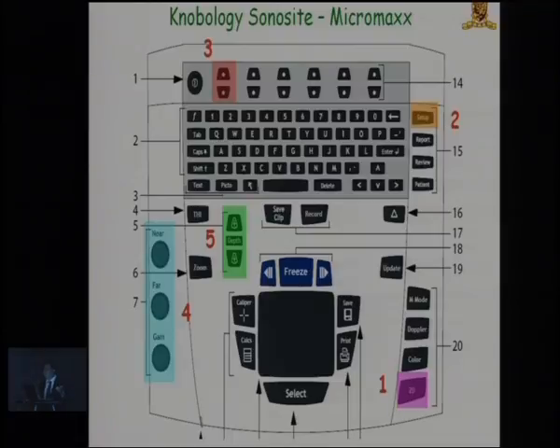Two, most machines come with preloaded setups. So they are already arranged for nerve scanning, soft part scanning, or abdominal scanning, or uterine scanning, etc. So if you select that, it makes the scan much better. Third is the resolution you need to choose. So you need to select the right probe, because now most probes are broadband. That means they have a range of frequencies that they will allow you. So you must use the appropriate frequency for the appropriate target area that you're looking at.